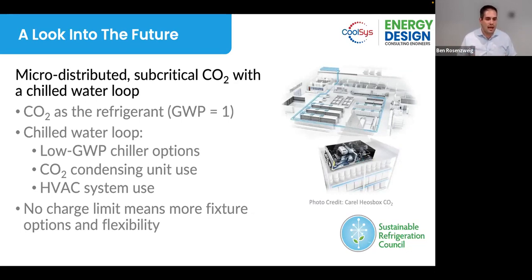So these have CO2 condensing units distributed throughout the store. The chilled water loop can be used with the air conditioning system and other options to create a really fully integrated HVAC and refrigeration design. And there wouldn't be any kind of charge limit at all because it's CO2, which means more fixture options and flexibility for the future. And one of the options that's currently being marketed and presented around this is the Carel Heosbox CO2 system, which was demonstrated a little earlier this year at Chillventa. So next slide, please.